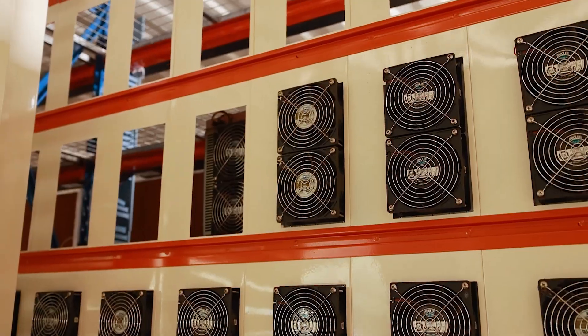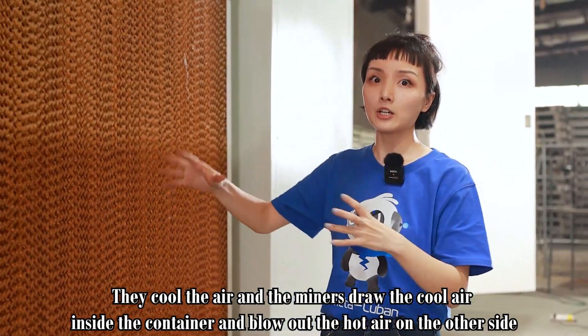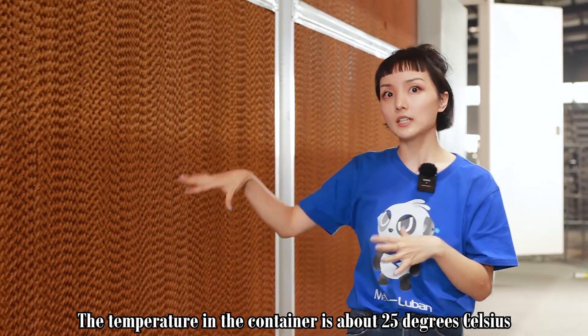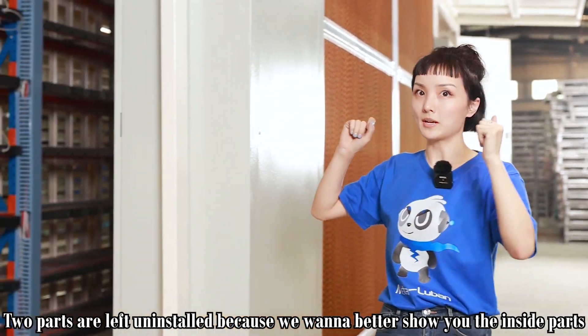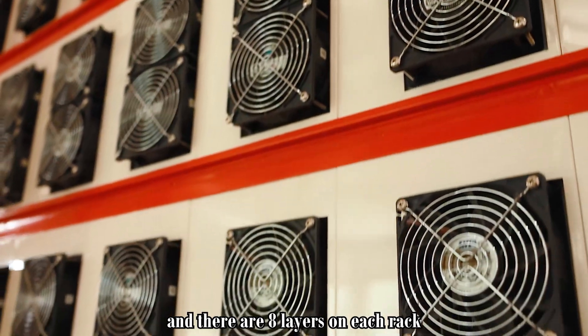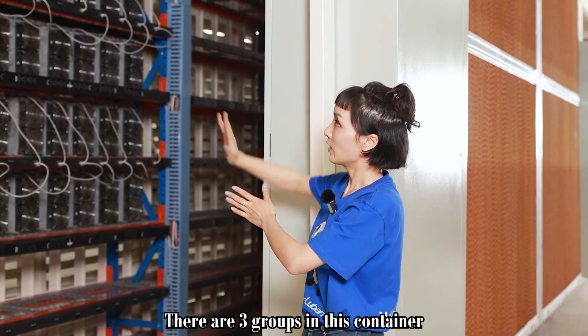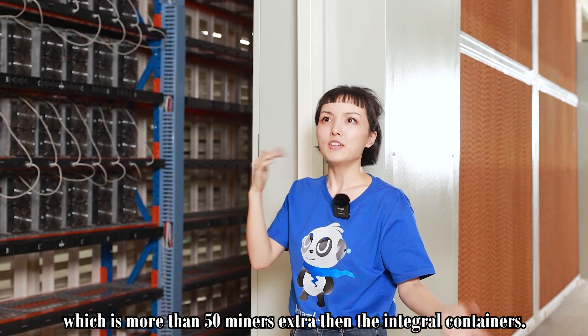Those are the water curtains — they cool the air and the miners draw the cool air inside the container and blow out the hot air on the other side, so the temperature in the container is about 25 degrees Celsius. Two parts are left uninstalled so we can better show you the inside. On one layer there are nine miners, there are eight layers on each rack, two racks together is one group, and there are three groups in this container. Guess how many miners there are — 432, which is more than 50 units extra compared to integral containers.